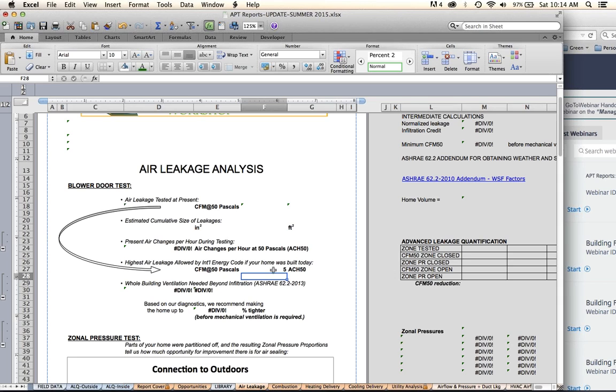Now, my state is on 5, not 3, so I would call it 5, because what I want to do is compare everything, all of the existing homes that I'm testing, to what they would have to be if they were built from scratch today as a D-minus grade, and that's 5 air changes per hour. If you want to be building to 3, that would be the highest air leakage allowed by International Energy Code if your home was built today. 3 is not probably going to change anytime soon. If you only work for badass clients, you could change it to 0.6 and make it passive house, whatever you want. So basically, you just need to go in here and change the calculation, obviously.